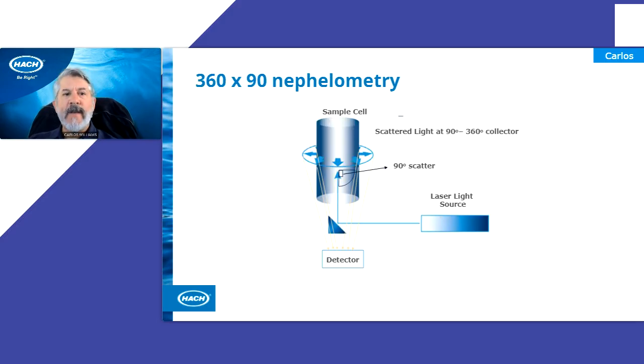So here's another method, the 360 by 90 nephelometry. Some of you may be familiar with Hach equipment. This is the basis of the TU5 series. So process analyzers are TU5400, TU5300, then the lab analyzers are TU5200. This was called the donut when we first designed it because it scatters light in 360 degrees and collects light in 360 degrees. And that 360 degree light detector picks up scattered light at a 90-degree angle. So once again, it works as a nephelometer.